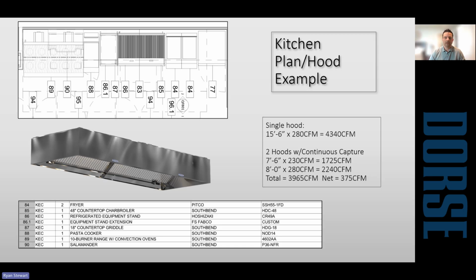It could be built in one section. Most of the major manufacturers can build up to 16 feet in one section. What I've found over the years, especially with existing buildings, is it's pretty difficult to get a hood that large into the building and back into the kitchen area. So usually over 12 feet, I'm going to design a hood as 2 sections with a continuous capture. So if you'll notice from the image there, it's two hood sections, but there's no wall inside the canopy itself. And what that's going to do is give us the greatest containment area and the lowest possible airflow.